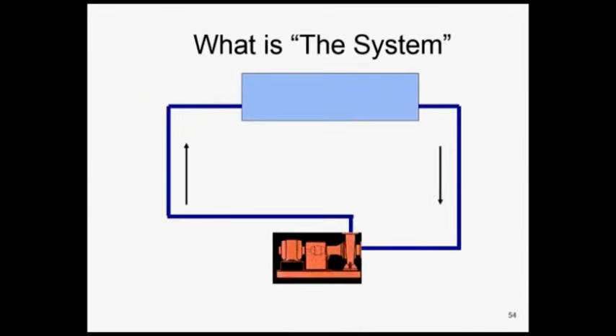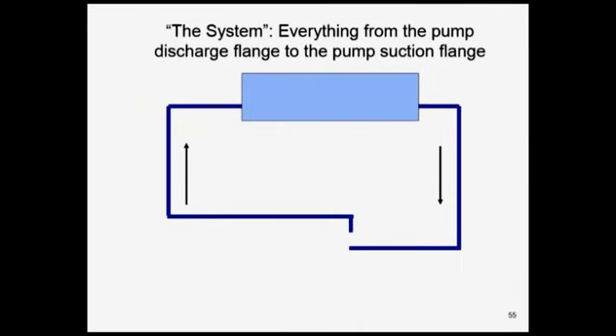Back to basics. So what is the system on a pump? It's everything from the discharge flange to the suction flange of the pump. That's considered the system. And if you start looking at the system, there's going to be some flow rate and some pressure drop involved in that piping. And once you do this, that's a fixed set of piping for that pump. When you change the position of the two-way valve, or the throttling valve, you're changing the system curve. But when you start it up and get everything fixed, you've got a fixed system curve, and it's not going to change until you change the position of the two-way valve.